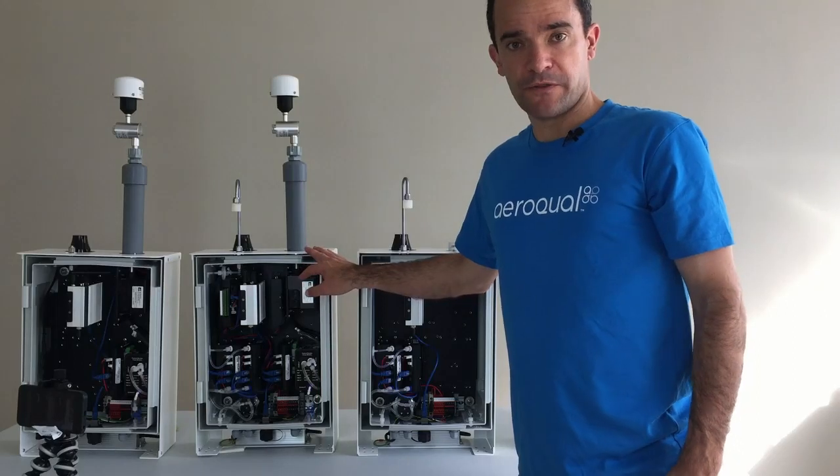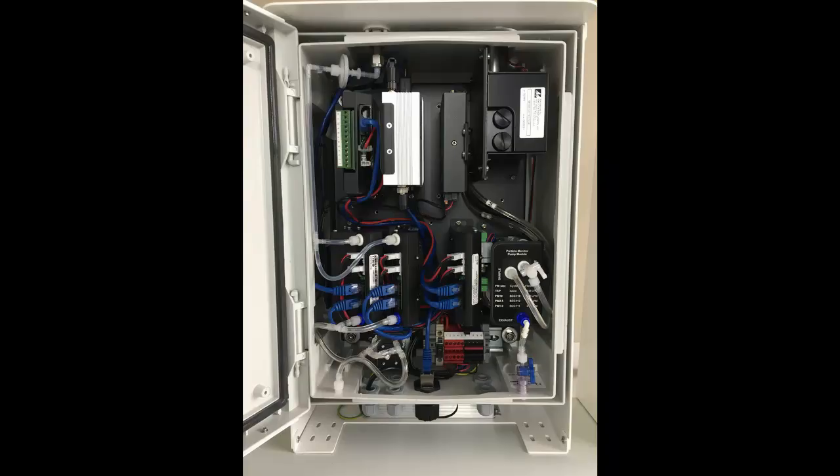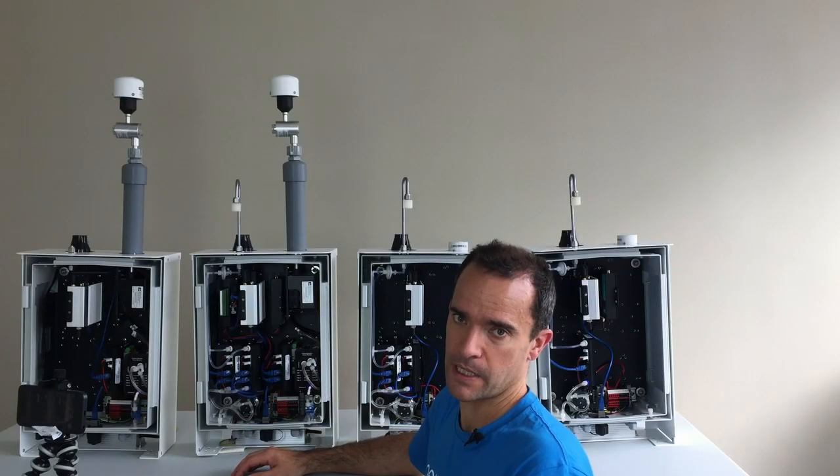Here we have an AQS1 which is configured with everything. So we have the nephelometer engine, we have the ozone module, we have the ox module, we have the auxiliary module for a weather station and of course the central PC. So this is a fully configured AQS1 with gas and with PM.